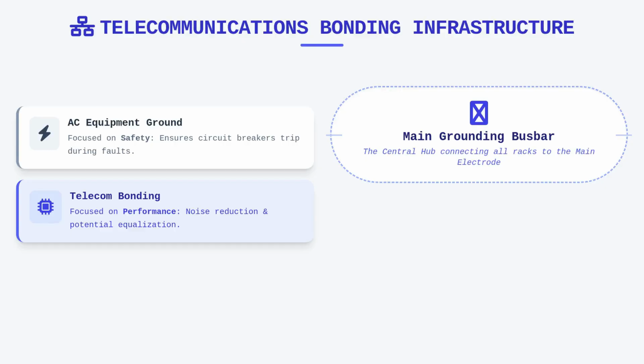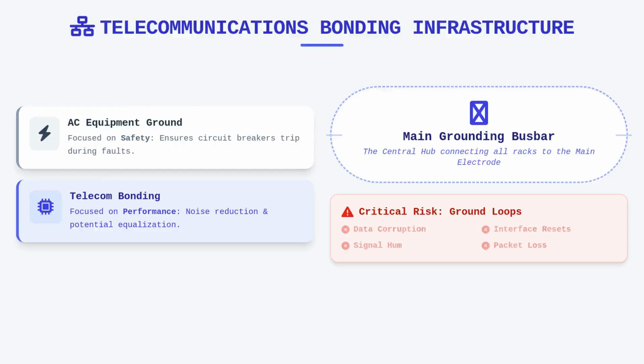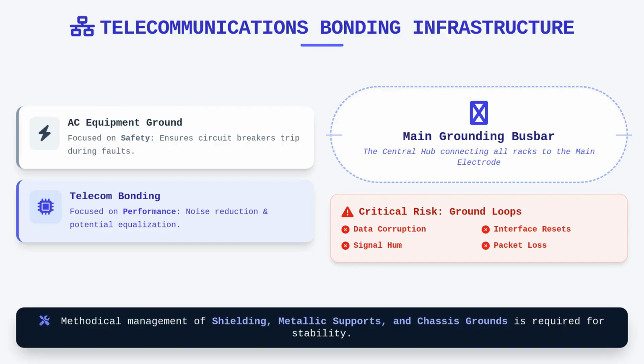When you design these systems, avoid creating circumstances that allow for ground loops, which occur when multiple paths to ground exist that have different potentials. A system burdened by ground loops can introduce unwanted hum and data corruption into sensitive telecommunications circuits, often manifesting as intermittent packet loss or interface resets. Effectively managing these potentials requires a methodical approach to how you connect your shieldings, metallic supports, and chassis grounds to the dedicated bus bars.